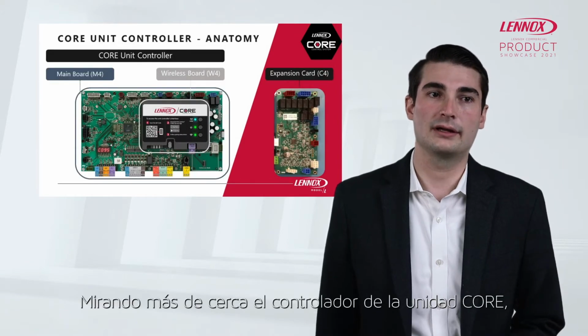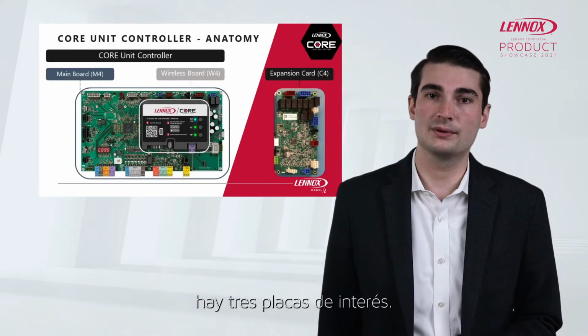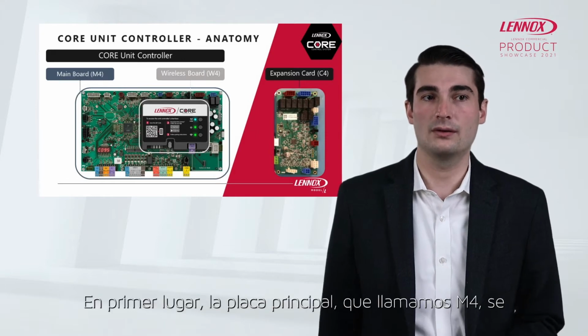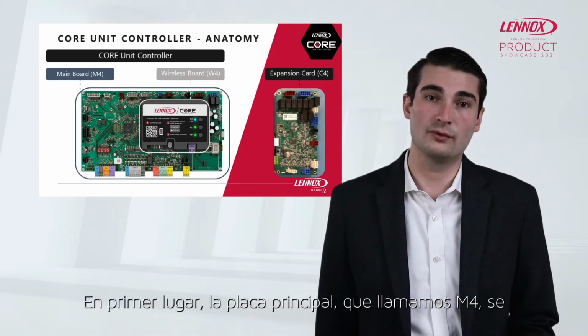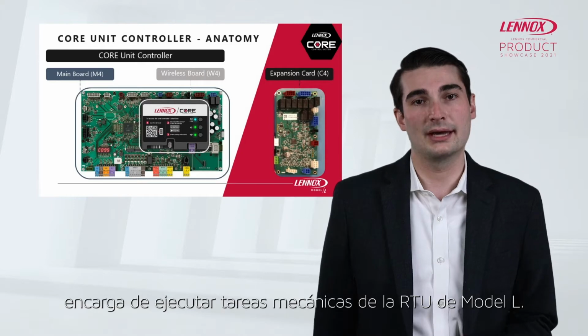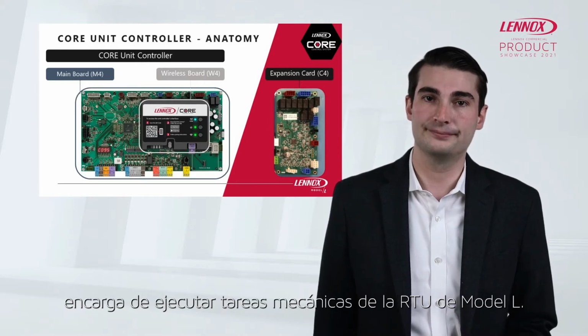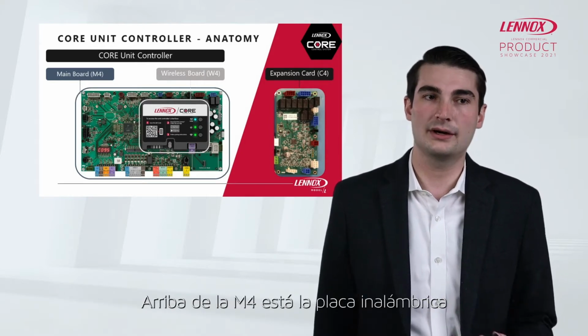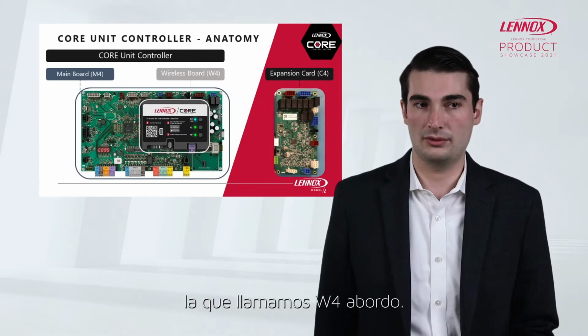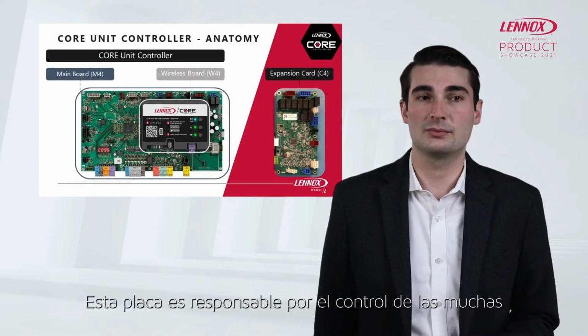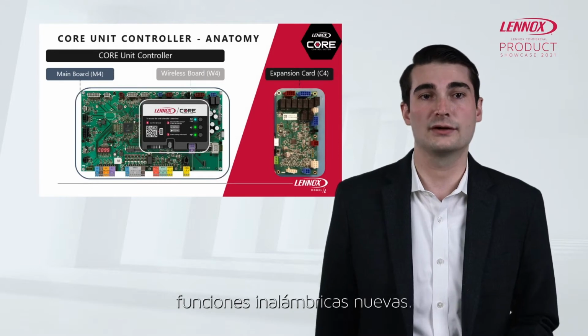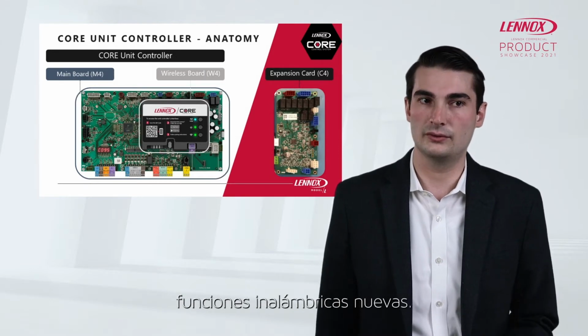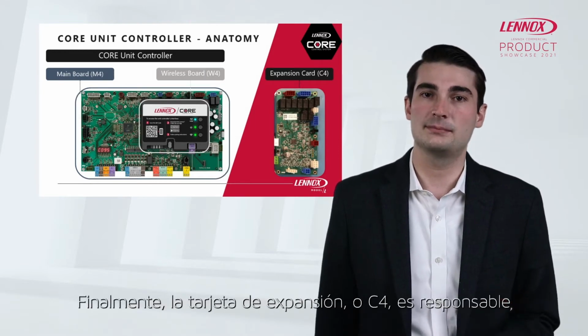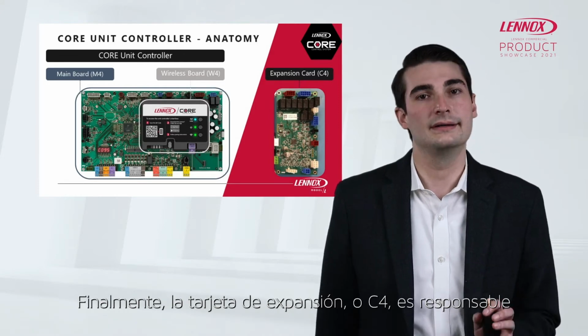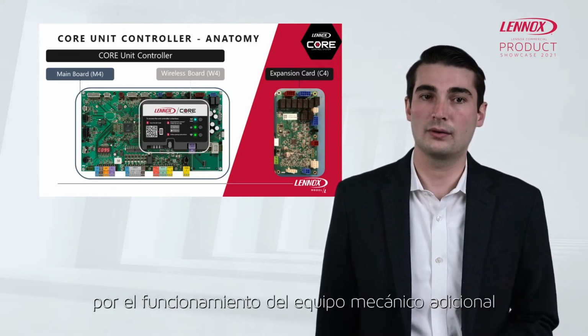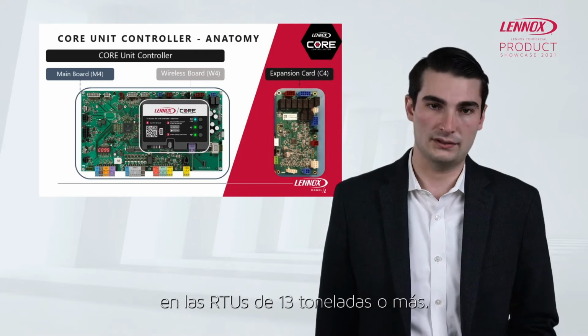Looking closer at the Core Unit Controller, there are three boards of interest. First, the main board, or what we call the M4, is responsible for running the mechanical parts of the Model L RTU. On top of the M4 is the wireless board, or the W4 board, responsible for control of the many new wireless functionalities available on this RTU. Finally, the expansion card, or C4, is responsible for running the extra mechanical equipment on the 13-ton and larger RTUs.